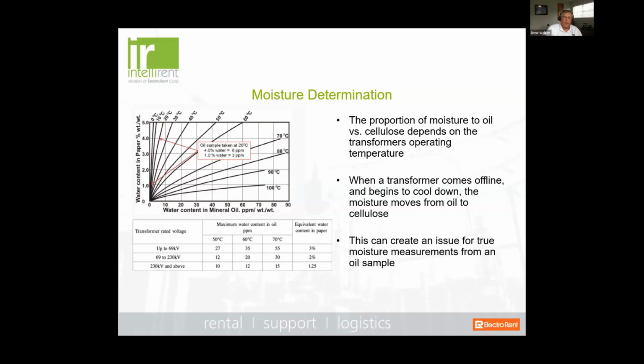What happens is you draw that oil sample through the ball valve. What's it going to do? It's going to cool down, right? So there's a lot of issues with regards to that. But what IEEE tells us is that depending on the type of transformer, you have a certain allowable maximum water content in ppm based on the operating temperature and what the equivalent water content in the paper should be.